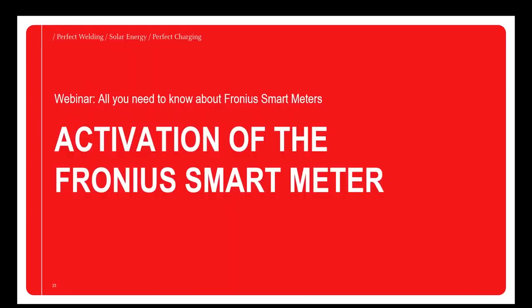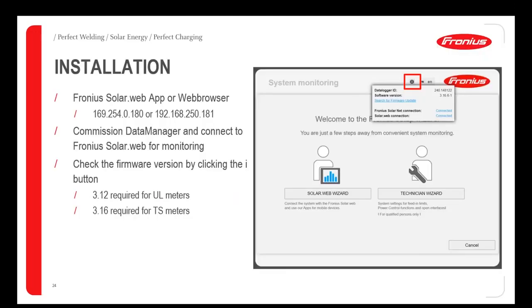So within the inverter, we then need to go to our data manager or our Gen 24 inverter. Connect as you would to commission a new system in SolarWeb, and we'll be using our technician wizard to detect the smart meter and incorporate that into our SolarWeb system.